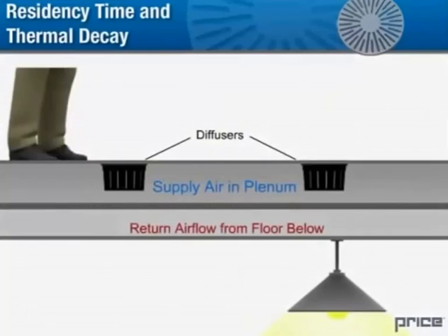When designing an underfloor system that uses a pressurized floor plenum, residency time of the supply air is an important factor. While in the plenum, the supply air is affected by the room above and below it.